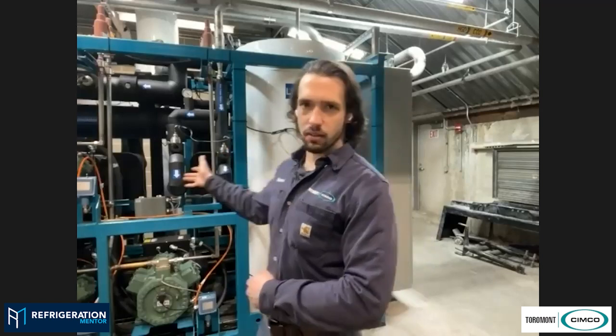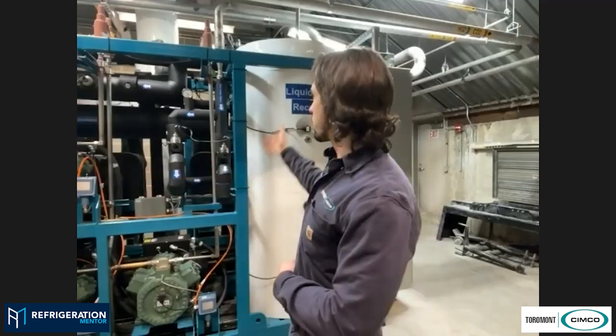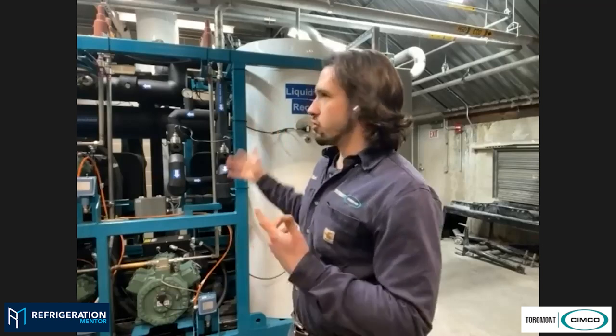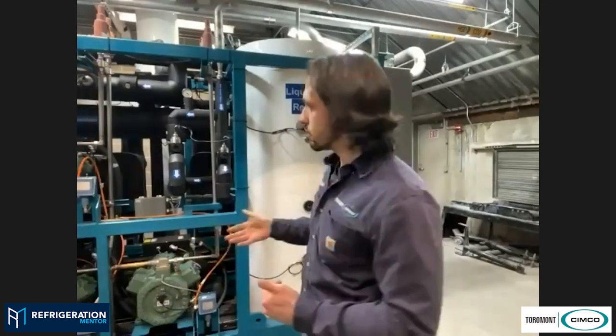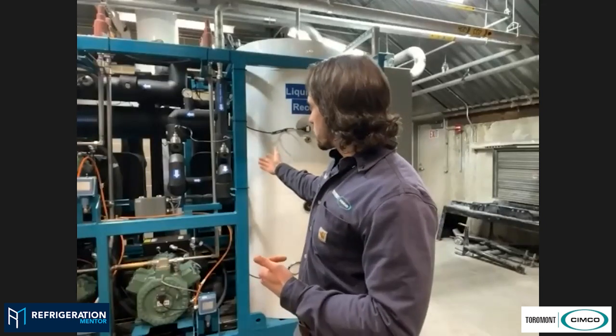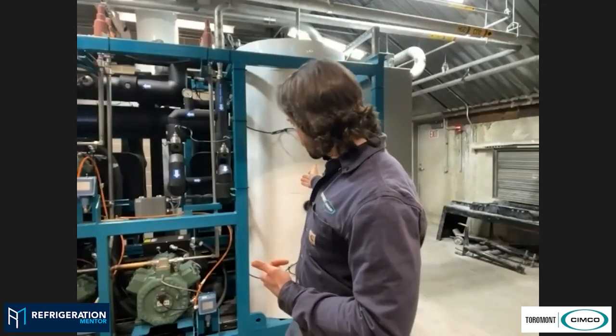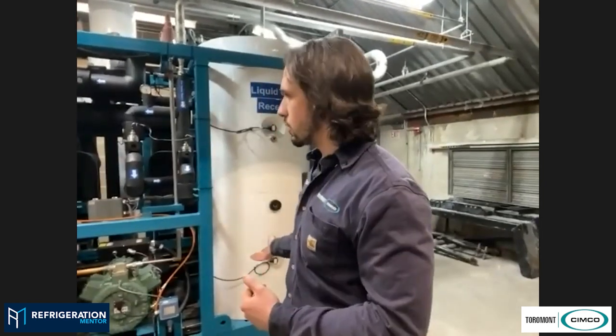But anyway, so obviously we have our HPV valves, those are like our metering device for the system. The system generally runs between 950 and 1200 PSI, I've never seen it higher than that. So we're metering our cooled gas into our receiver, where we get liquefaction of our CO2.